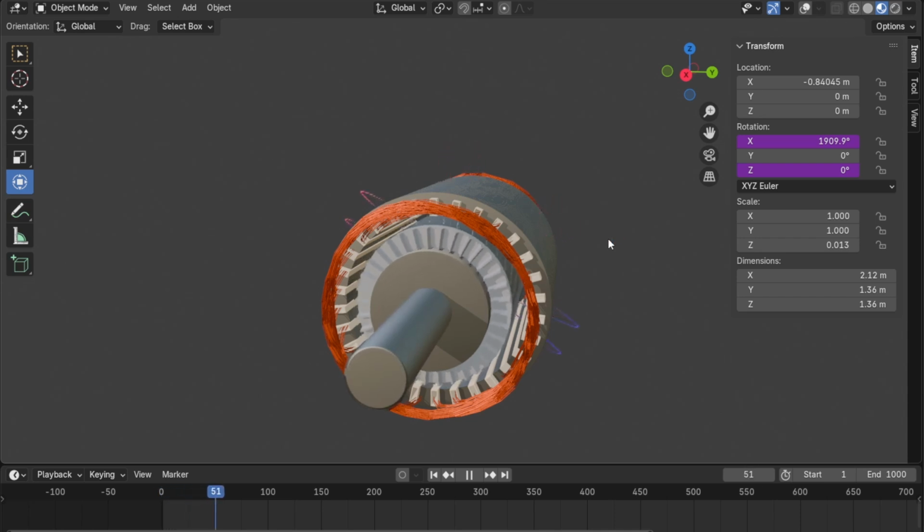If our magnetic fields are less strong, we get a reduction in torque, and we can assume that our mechanical load is going to be the same. It's going to be constant and not changing very much. And so that means our rotor has no choice but to slow down. Okay? But think about it. What happens to our rotor if it slows down? What happens on locked rotor conditions?